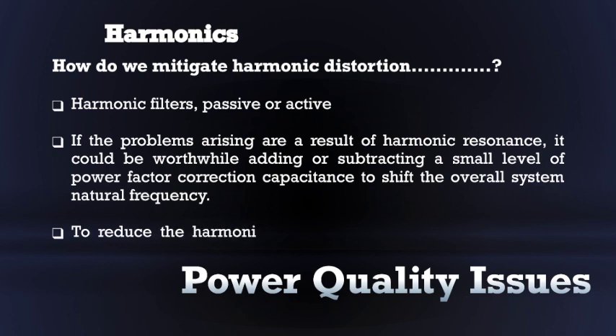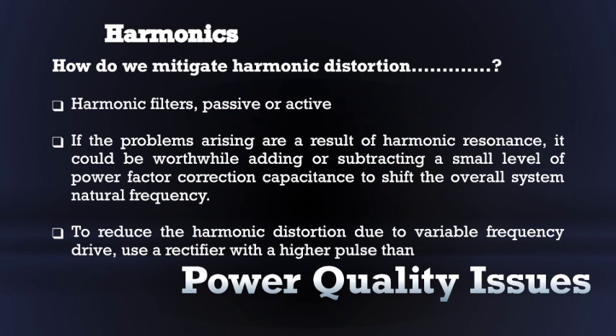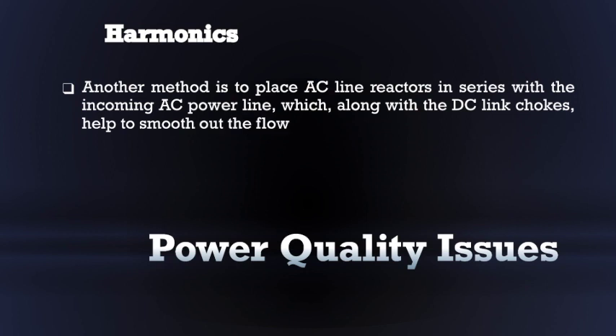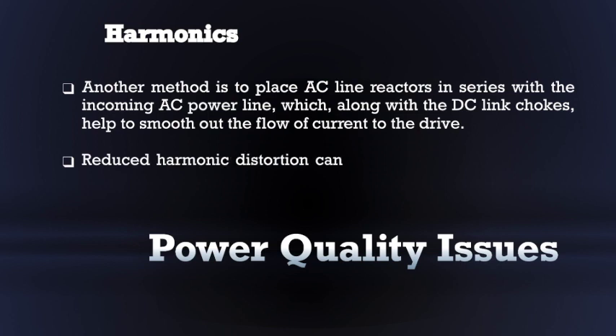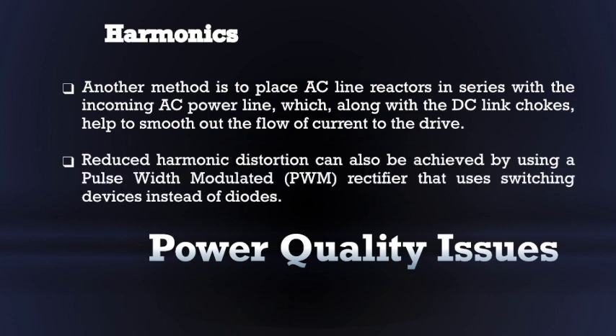Also, to reduce the harmonic distortion due to variable frequency drive, use a rectifier with a higher pulse than 6. As we go for higher pulse, harmonic content naturally reduces. Another method is to place an AC line reactor in series with the incoming AC power line, which along with the DC link chokes help to smooth out the flow of current to the drive. Reduced harmonic distortion can also be achieved by using a pulse width modulated rectifier that uses switching devices instead of diodes.